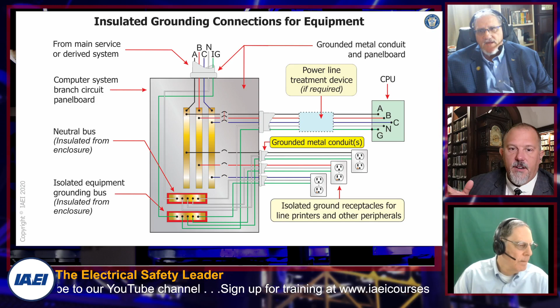You show the red backing behind that copper bus. When I look at this picture, I see it - it's physically right here. I see this plastic piece here, and this backboard, none of which is conductive, and it's separating this bar from the enclosure. That solidifies it for me.